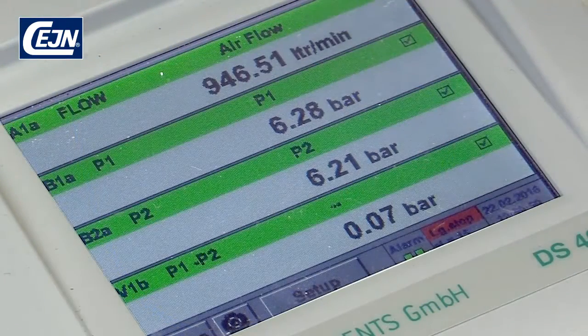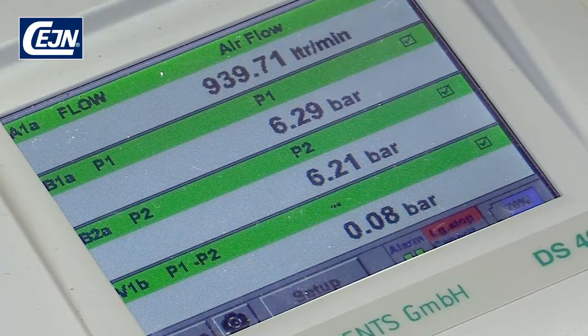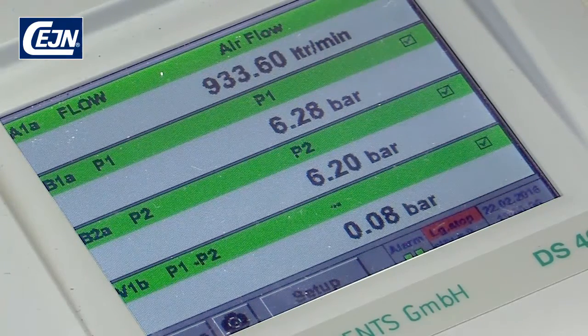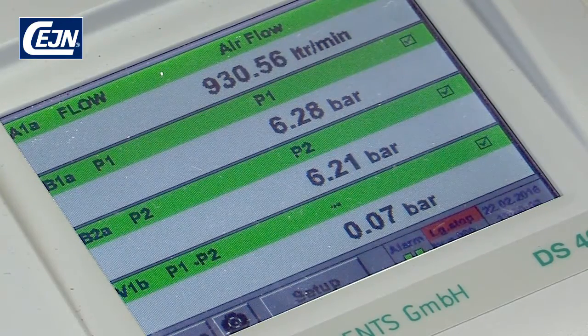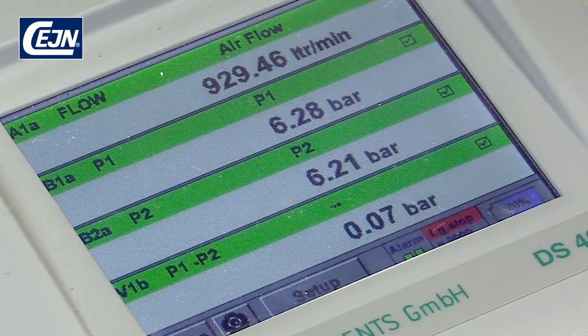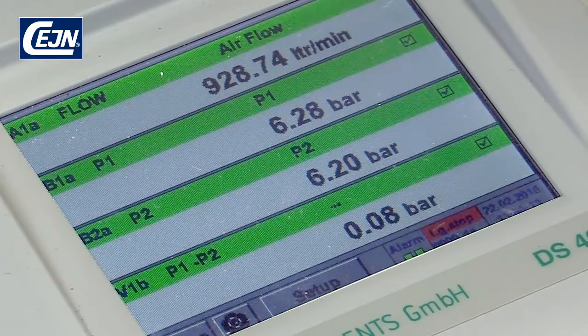Use the valve to adjust how many litres you want to flow through. In this case, we want it to be around 900 litres. On the screen, you can see the flow, pressure at P1 and P2, and the difference between P1 and P2.